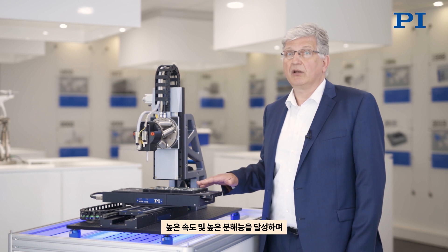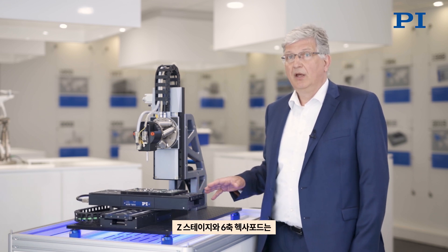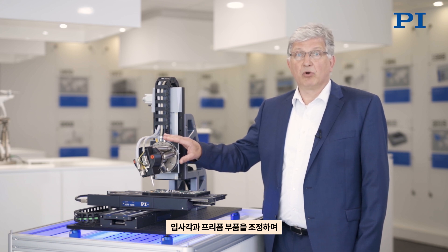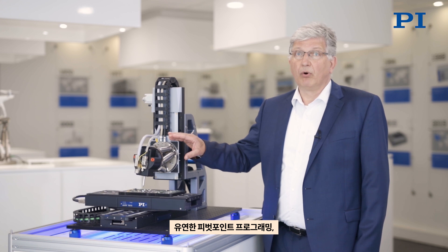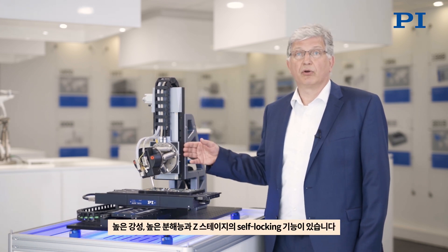The key features of this system: for the x-y stage, it is linear motor driven, therefore achieving high speed, high resolution, and 24-7 capability. The z-stage plus the hexapod offers 6-degree adjustment for angle of incidence and free-form components, flexible programming of the pivot point, high stiffness, high resolution, and for the z-axis it is self-locking when powered off.